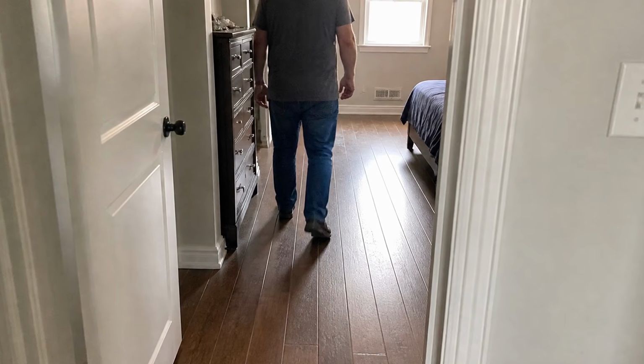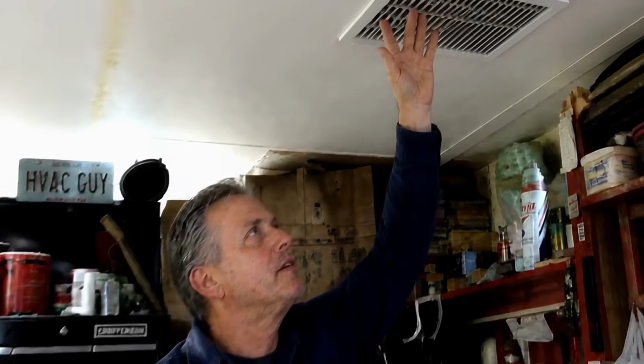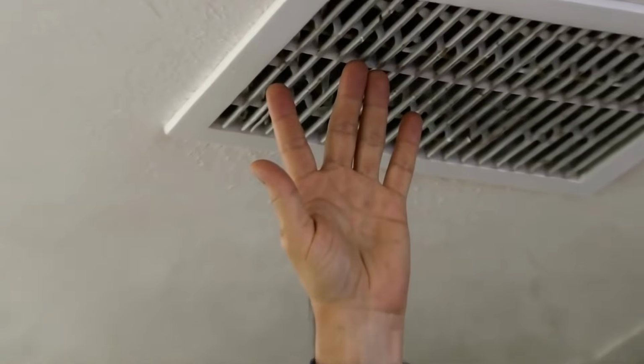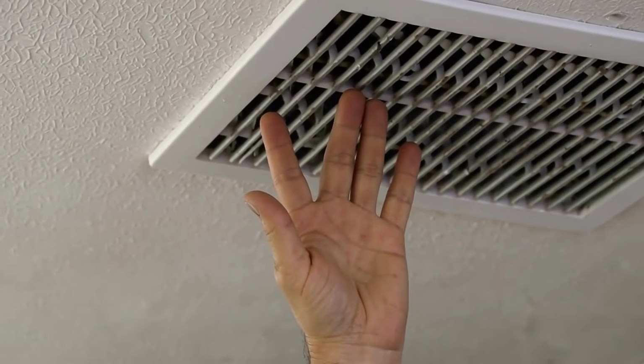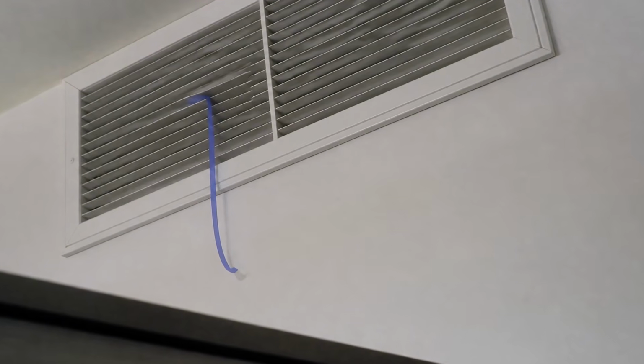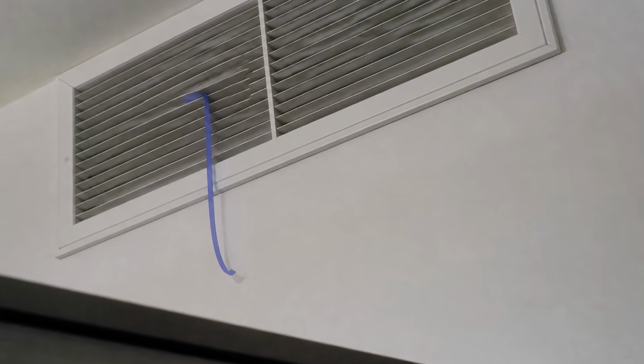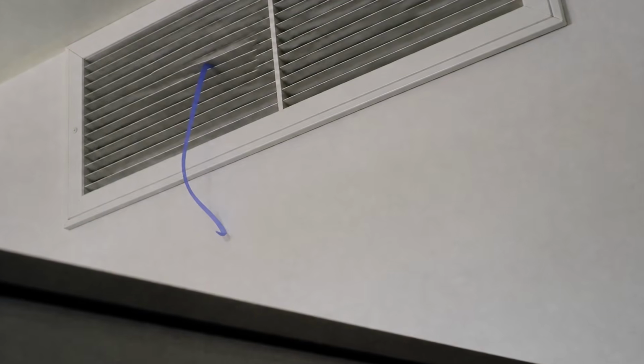And here's the part I love: you do not need a contractor to tell you which camp you're in. On the next hot day, with the system running, walk to the room farthest from the unit, put your hand flat on the vent, and feel how hard the air is actually pushing. Weak, warm, barely moving in the far rooms usually means the ducts are losing your air on the way there.